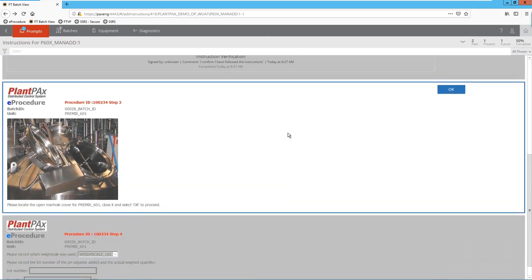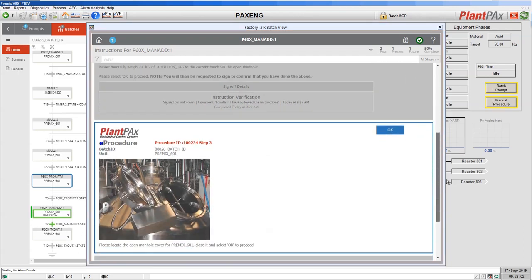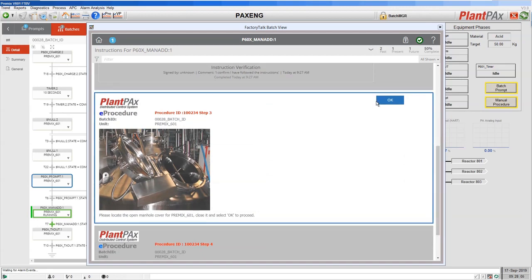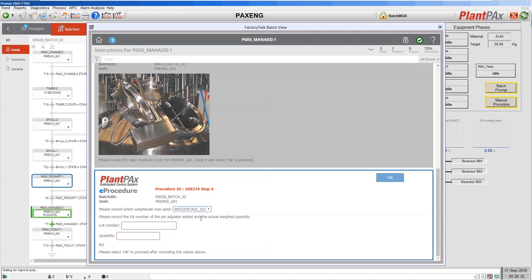Then we move on to the next step. Let's go back to our integrated interface in FactoryTalk View — again you can see it's showing the same information. I'm going to move down to the next step where I'm being asked to go and close the manhole cover, and I'll confirm that I have done that. Then we move on to the final step. An eProcedure is not just about instructing people to do things and recording signatures — you can also use it to collect information from the user. Here we're being asked to confirm which weighscale was used. The system knows that, because we're running on this particular premixer, there are only three weighscales we can choose from.